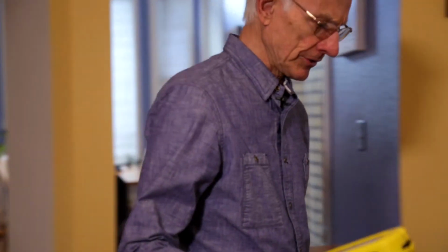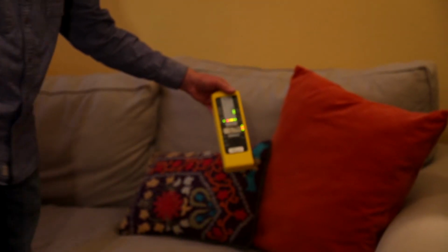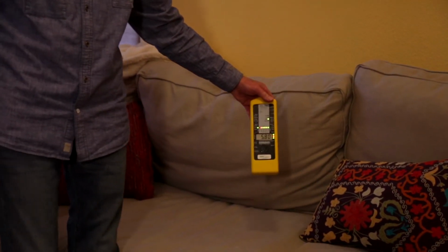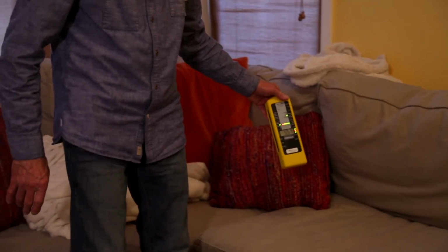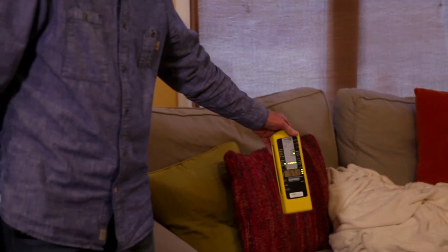We've placed a load on the outlets in the house looking for miswiring or parallel neutral paths, and we seem to have found one. So we're here in the family room with the meter just to show the effect that these sorts of things have on the level of field. So if we come over to the area where people are sitting on the couch watching TV or conversing, we're noticing we're running a 5 milligauss field, roughly 500% higher than the level we'd like to see people at in the areas where they rest and play.